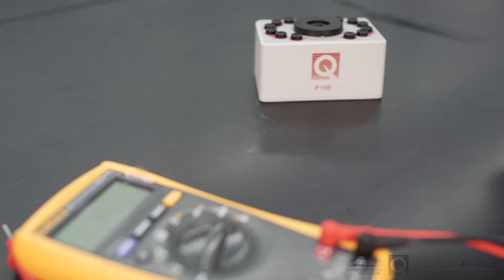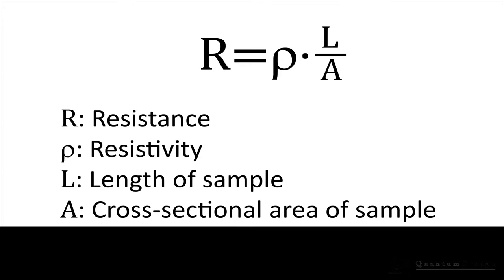Here's a piece of copper wire that we have silver painted to the pads on the VersaLab measurement puck. The resistivity of copper is 1.68 times 10 to the negative 8 ohm meter. Recall that a material's resistance is determined by its resistivity multiplied by the ratio of the length to the cross-sectional area of the material. Using this 4 centimeter length of copper, I expect the resistance to be around 0.6 milliohm. Let's plug this into the diagnostic puck box that comes with every QD instrument and find out.